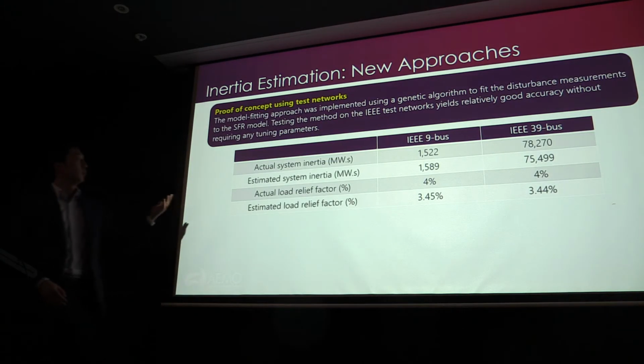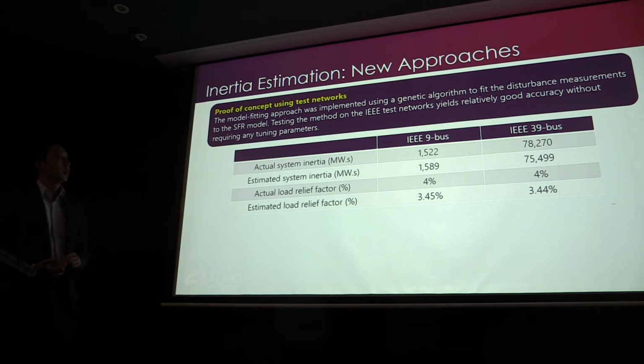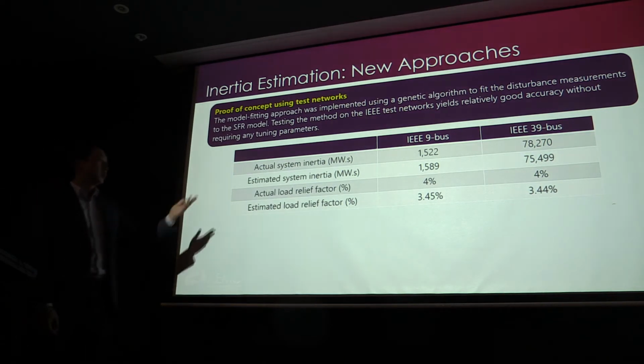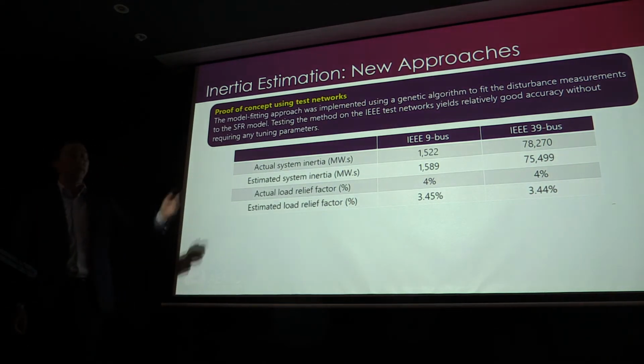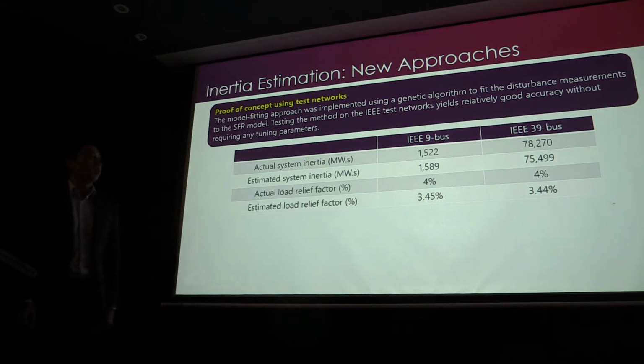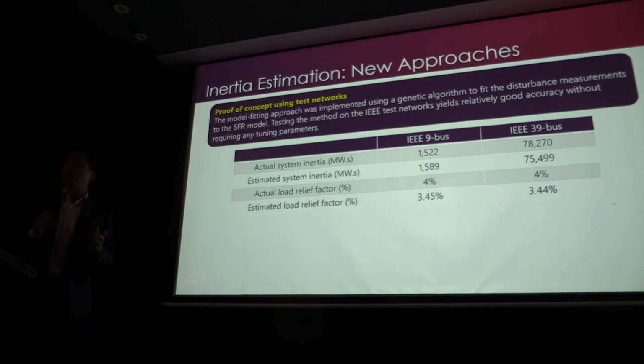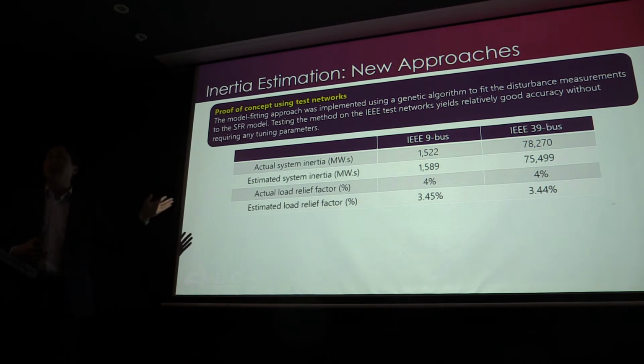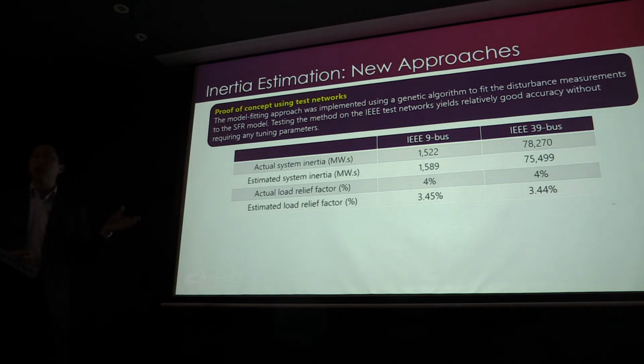And we just did the proof of concepts with the IEEE 9 bus and the 39 bus, and you can see it's pretty close. Where it was 1522, we're getting 1589, and the load relief factors were also pretty close. On the 39 bus, we're not too far out, probably a slight overestimate, but it's better than the other ones where you don't know where you are at. How do you choose the polynomial order or the sliding window? In this case, you're not choosing anything. You're just running it through the algorithm, and then off you go. So it probably gives you a better order of magnitude estimate.